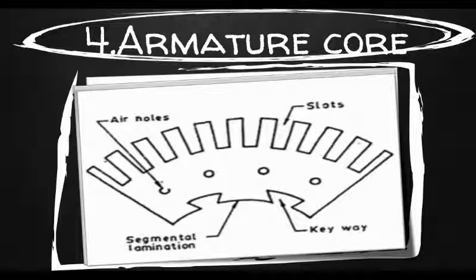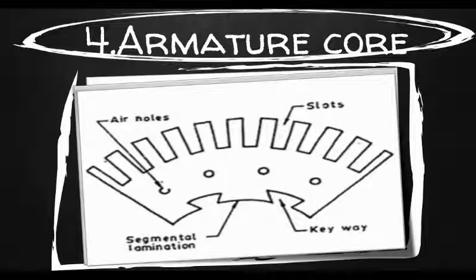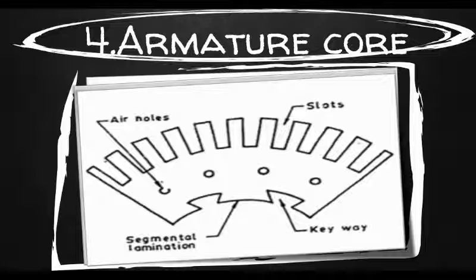Up to diameters of 1 meter, the circular stampings are cut out in one piece. But above this size, these circles of such thin sections are difficult to handle because they tend to distort and become wavy when assembled together. Hence, the circular laminations instead of being cut out in one piece are cut in a number of suitable sections or segments, as you can see in the figure, which form part of a complete ring. The purpose of using laminations is to reduce the loss due to eddy currents — thinner the laminations, greater the resistance offered to the induced EMF, smaller the current and lesser I²R loss in the core.